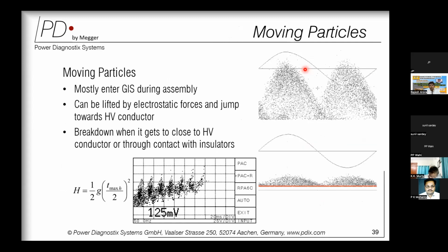Same in case of a moving particle. If we see this kind of defect, which is called a moving particle, then what we need to do is apply another technique called the acoustic technique and understand to what height these moving particles are jumping, because the electrostatic force makes the particle jump towards the HV conductor. That means from the base of a GIS they will jump under the influence of high voltage, and when a particle touches the high voltage conductor, the breakdown will happen.